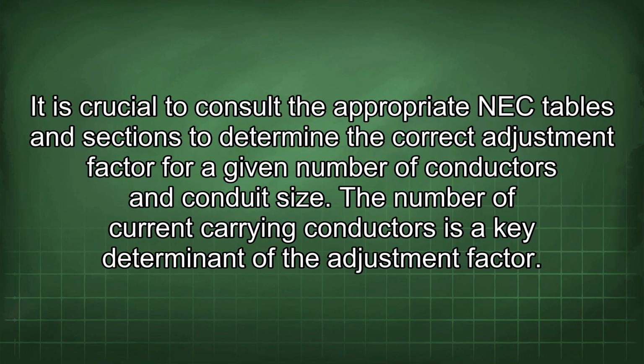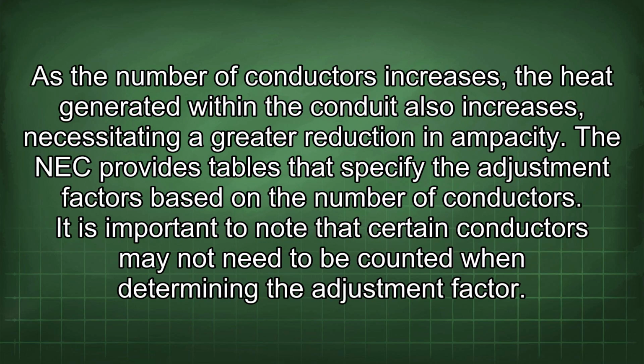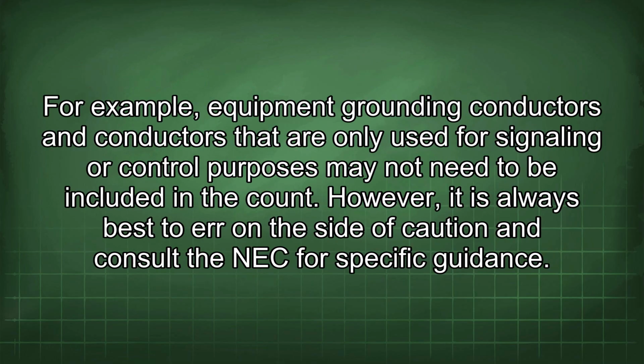It is crucial to consult the appropriate NEC tables and sections to determine the correct adjustment factor for a given number of conductors and conduit size. The number of current-carrying conductors is a key determinant of the adjustment factor. As the number of conductors increases, the heat generated within the conduit also increases, necessitating a greater reduction in ampacity. The NEC provides tables that specify the adjustment factors based on the number of conductors. It is important to note that certain conductors may not need to be counted when determining the adjustment factor. For example, equipment grounding conductors and conductors that are only used for signaling or control purposes may not need to be included in the count. However, it is always best to err on the side of caution and consult the NEC for specific guidance.